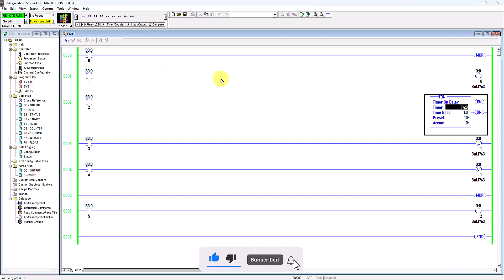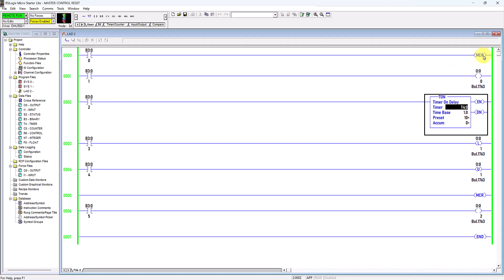What happens is: if I toggle a bit for this switch, the switch will be triggered from normally open to closed, and then the virtual power can flow through this rung to energize the MCR or Master Control Reset instruction. This MCR will have control over the rungs below it — from this rung all the way to the next MCR rung. So the control area is from the first MCR rung to the last MCR rung only.